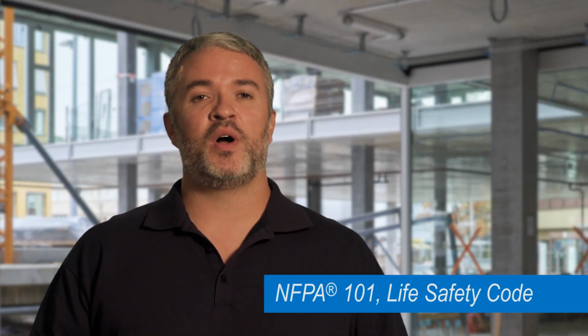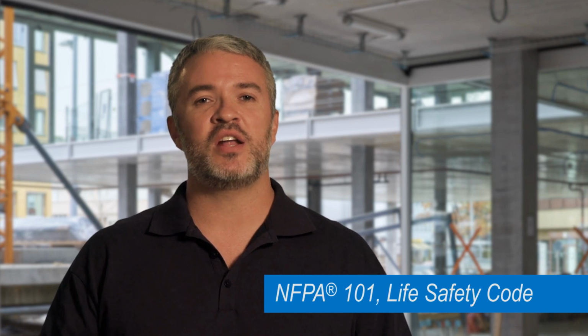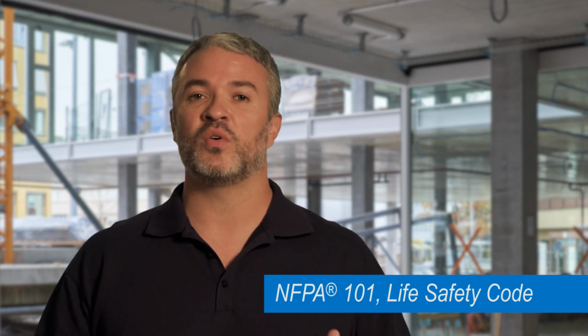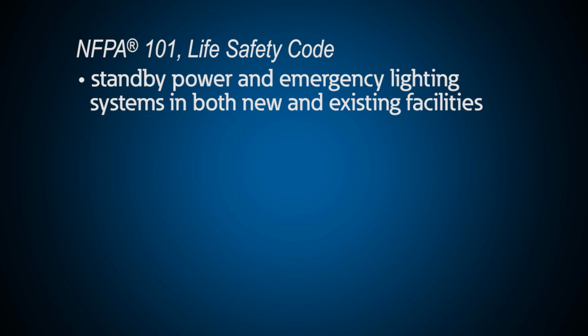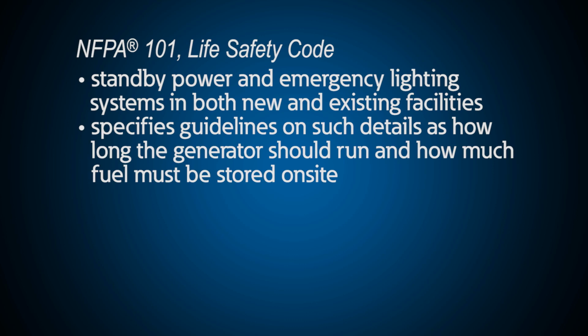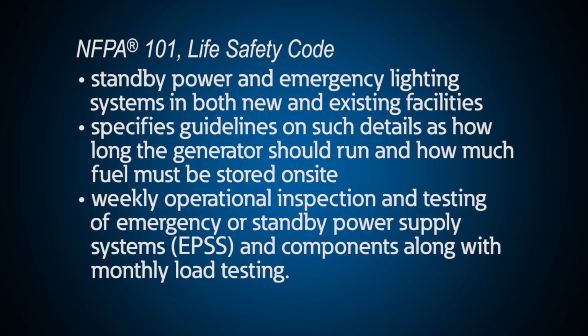The NFPA 101 is the Life Safety Code. The Centers for Medicare and Medicaid Services, or CMS, currently require healthcare facilities to comply with the NFPA 101. This code includes requirements for standby power and emergency lighting systems in both new and existing facilities, specifies guidelines on such details as how long the generator should run and how much fuel must be stored on site, weekly operational inspection and testing of emergency or standby power supply systems and components along with monthly load testing.